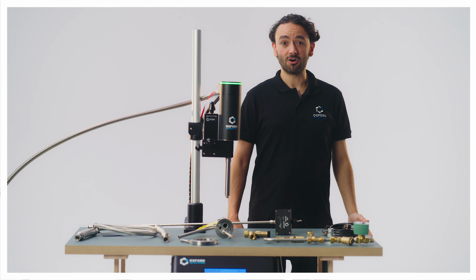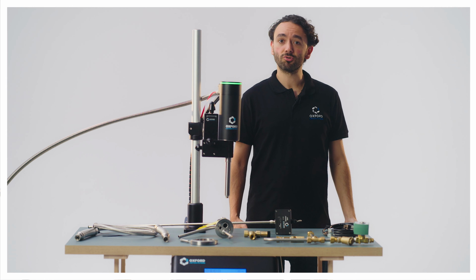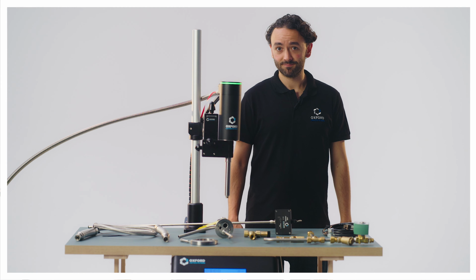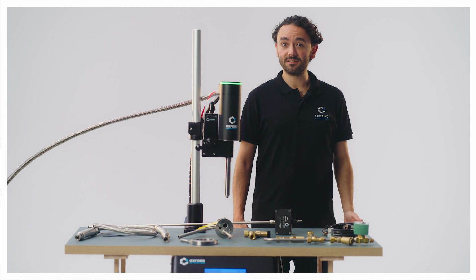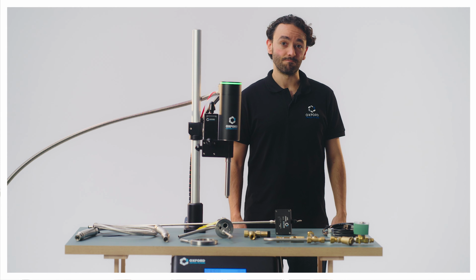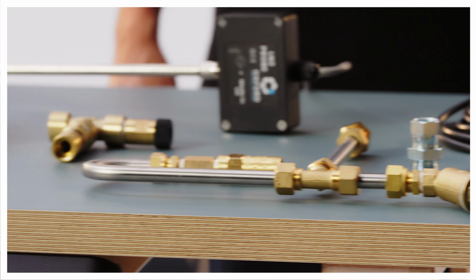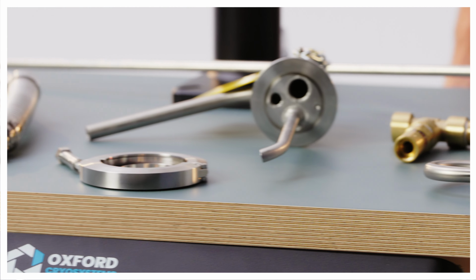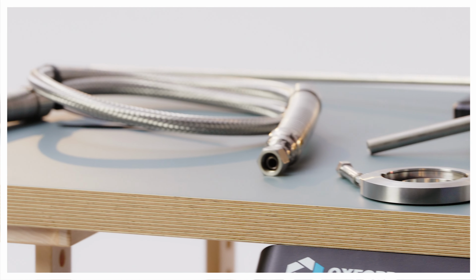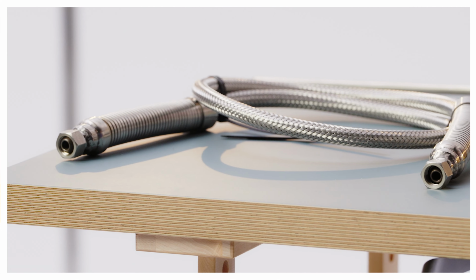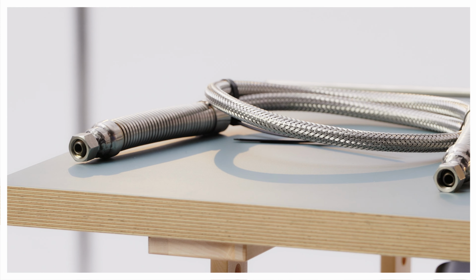The Autofill is an optional accessory that connects a storage vessel to your 60-litre dewar. It has a liquid level sensor probe which connects to the GSM. When the level of liquid nitrogen in your dewar reaches 20%, the Autofill opens a valve, allowing liquid nitrogen to fill your dewar back up to 80%.